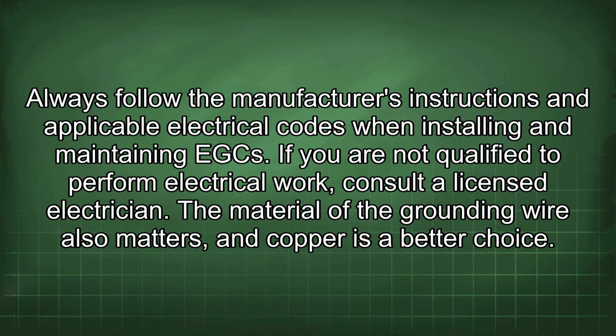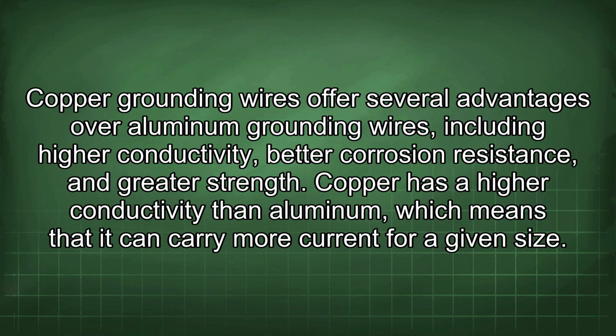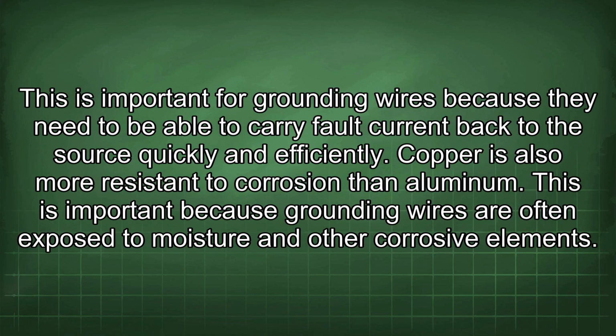The material of the grounding wire also matters, and copper is a better choice. Copper grounding wires offer several advantages over aluminum grounding wires, including higher conductivity, better corrosion resistance, and greater strength. Copper has a higher conductivity than aluminum, which means that it can carry more current for a given size. This is important for grounding wires because they need to be able to carry fault current back to the source quickly and efficiently. Copper is also more resistant to corrosion than aluminum.